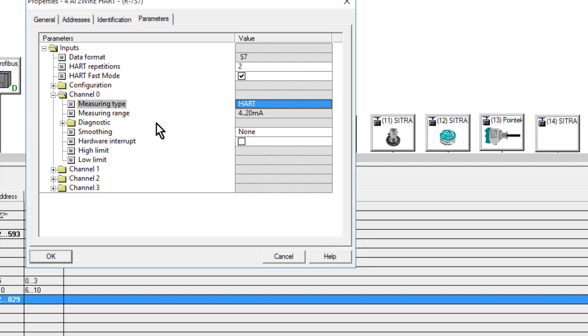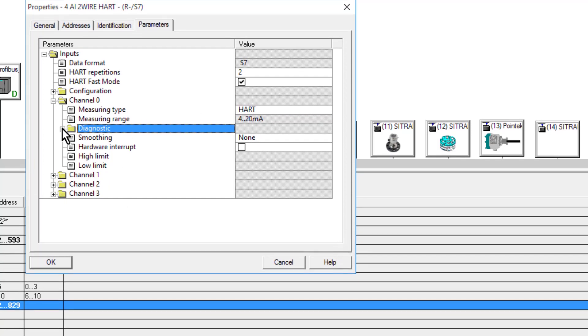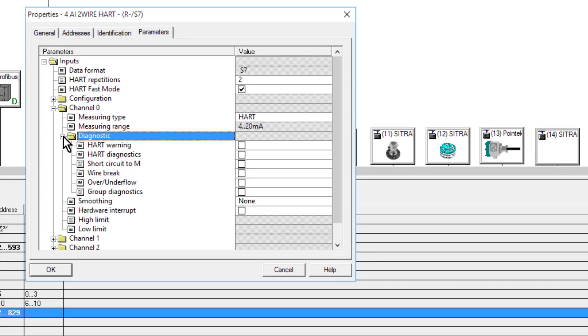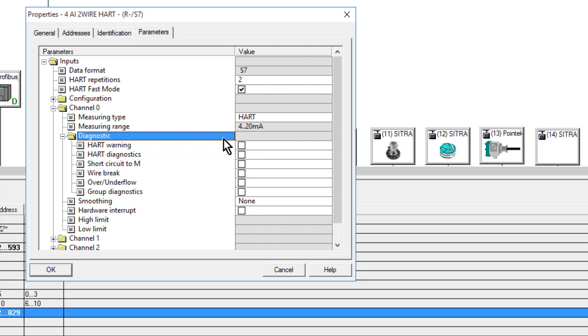I don't need to do anything else for that. I don't need to map any HART variables. I can still enable HART diagnostics or standard analog diagnostics for that input.